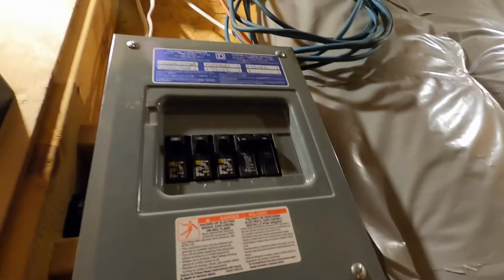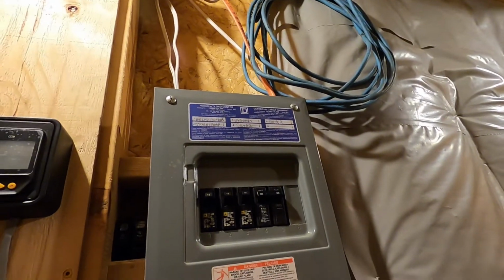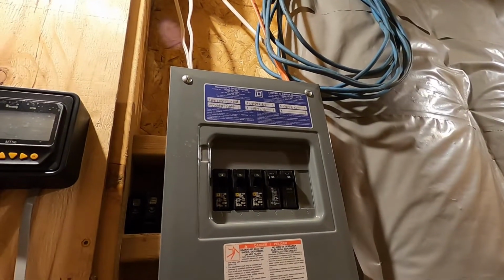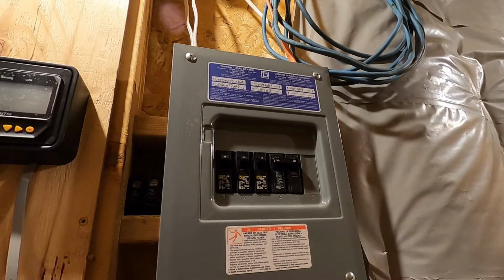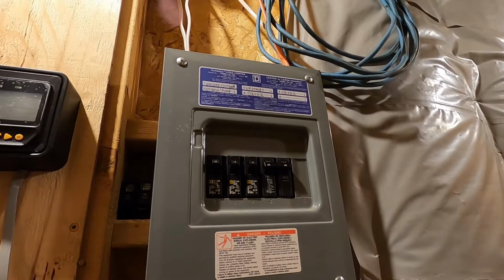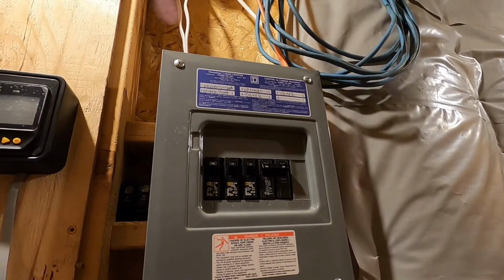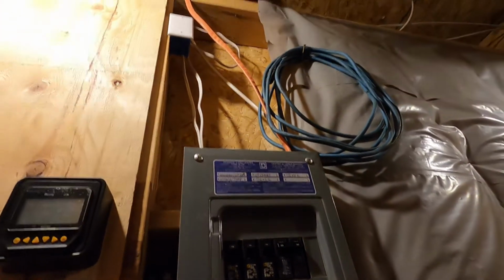And then here is your AC output, output 1, output 2, black and red, and then the neutral. I use this yellow and green wire for the neutral, and that's wired into this circuit breaker panel just like you would have a normal 240 input with a hot 1, hot 2, and a neutral, and ground, and then wires go out from there all over the house.